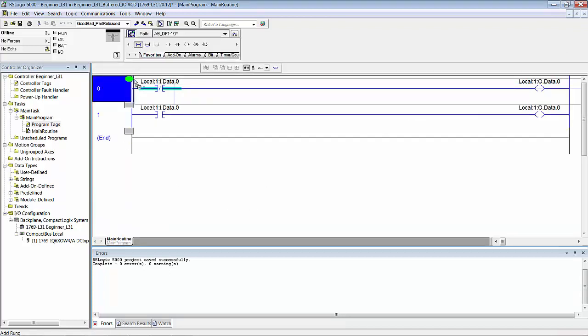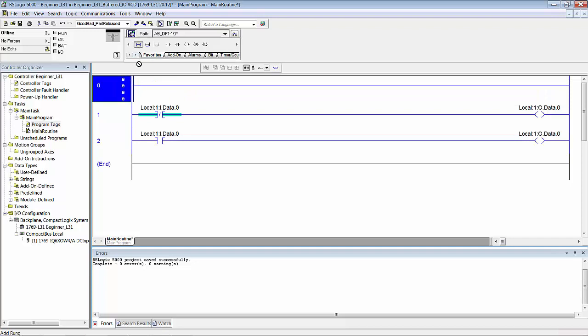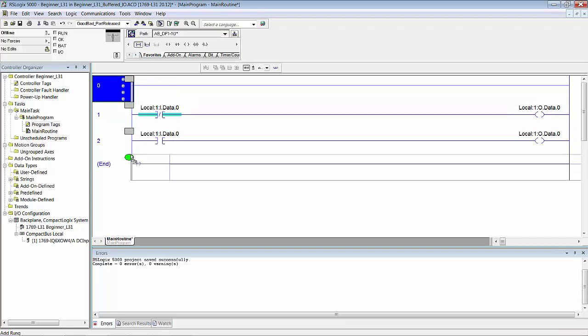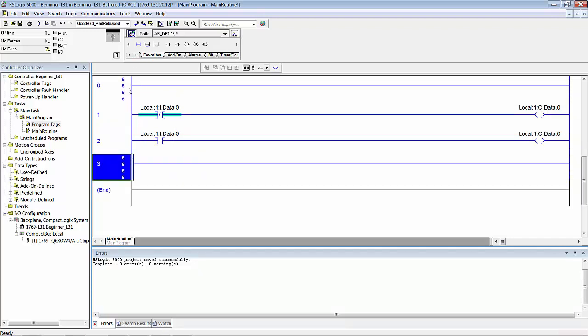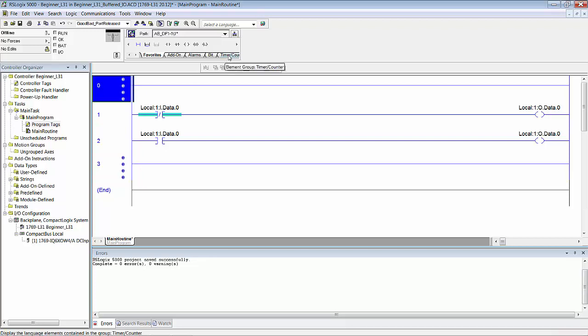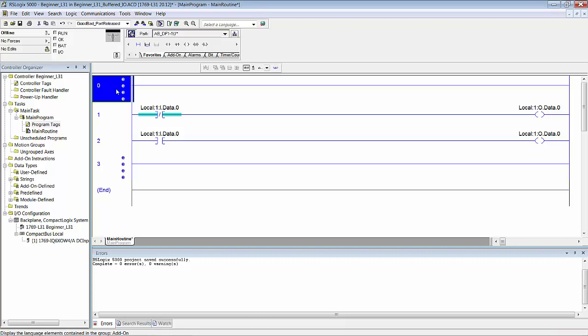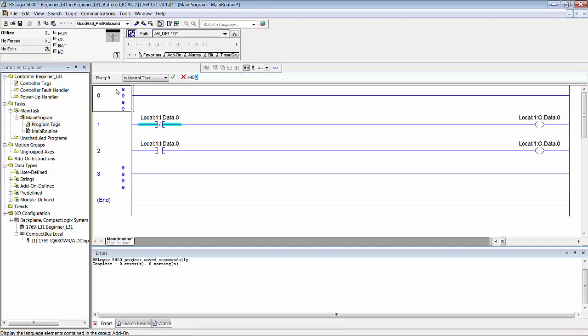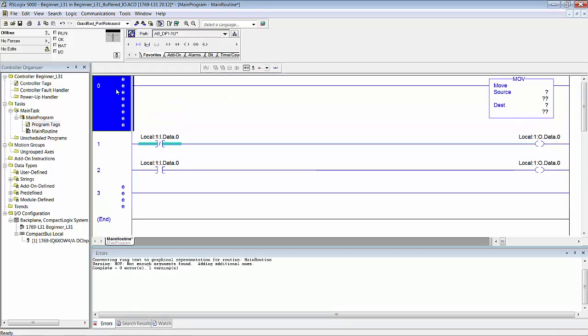I'm going to drag a rung down here and drag another one down here. In the top rung, there's several ways you can do this to get the right instruction. I could just type in MOV and that would have worked. I'll do that on that rung: MOV, enter. See, there's a move instruction. It's really a word copy—you're not moving it. If you move something then it's where it is now and not where it was before. So it's not really a move, but word copy—that acronym was already used so they use move. A MOV instruction is not really move, it's a word copy.